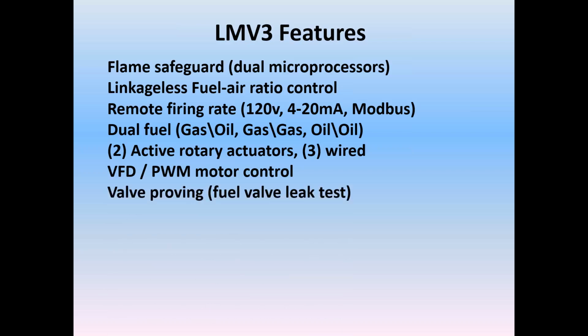It has built-in valve proving that you can use or not use at your discretion. Valve proving is an awesome way to do valve leak tests. It can be used in addition to or in lieu of a vent valve. And it is built into the LMV3. Simply by adding a gas pressure switch between the valves, you can do valve proving.